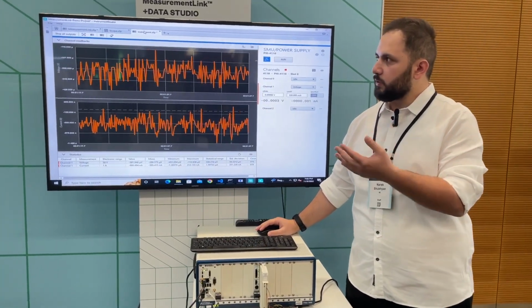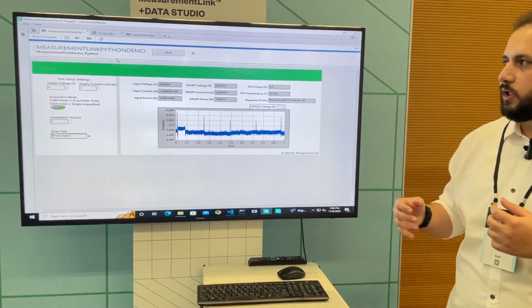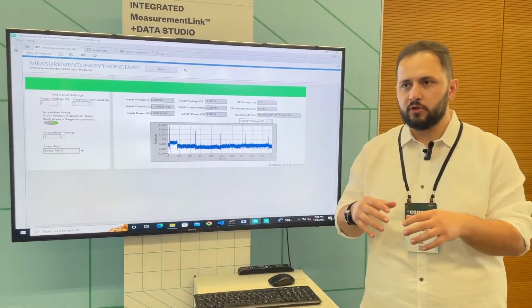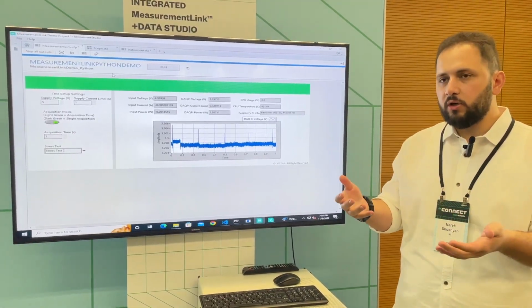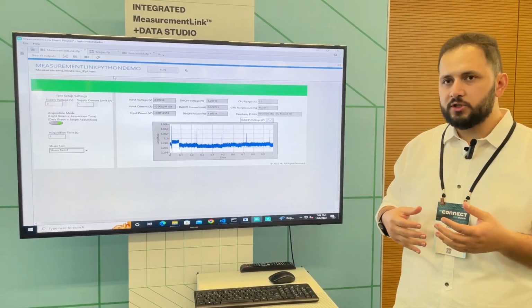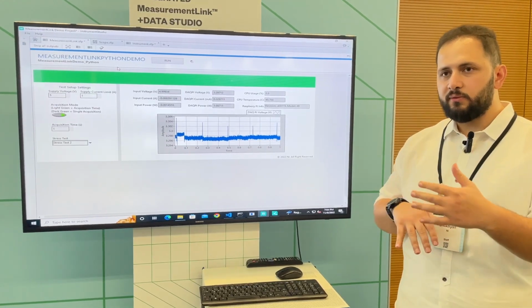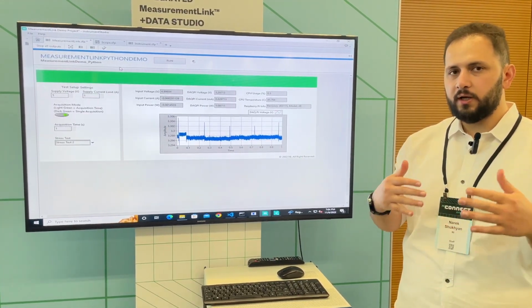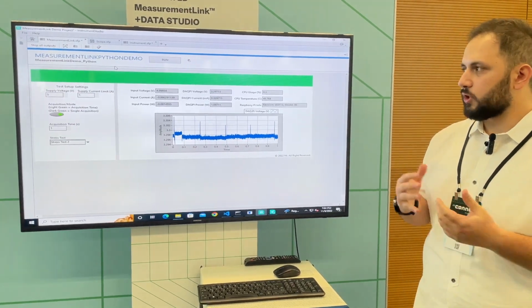The Measurement Link is the addition to Instrument Studio, where we enable not just controlling simple instruments, but also putting the measurement code into Instrument Studio for interactive control. Most validation engineers use a lot of scripts or code that they've written to control the instrument in a certain way, in a certain sequence, to do the test measurement that they're looking for.